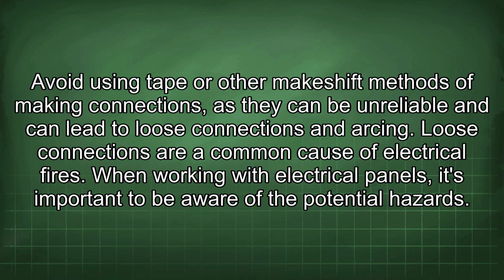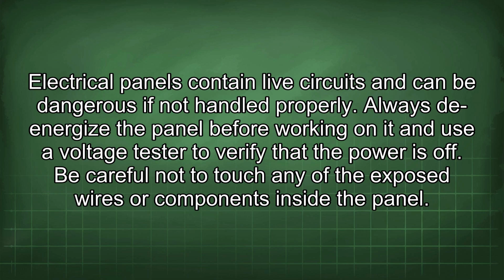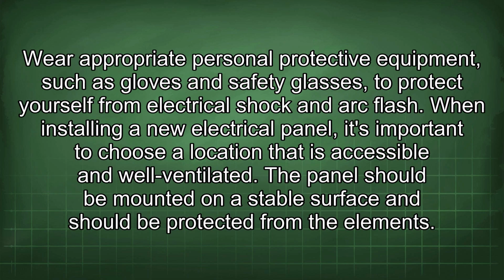When working with electrical panels, it's important to be aware of the potential hazards. Electrical panels contain live circuits and can be dangerous if not handled properly. Always de-energize the panel before working on it and use a voltage tester to verify that the power is off. Be careful not to touch any of the exposed wires or components inside the panel. Wear appropriate personal protective equipment such as gloves and safety glasses to protect yourself from electrical shock and arc flash.